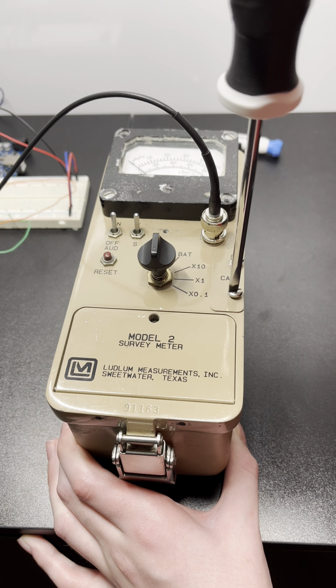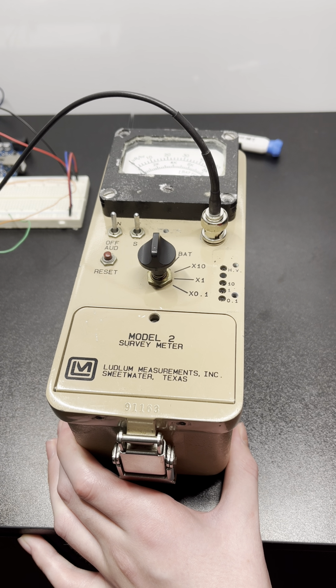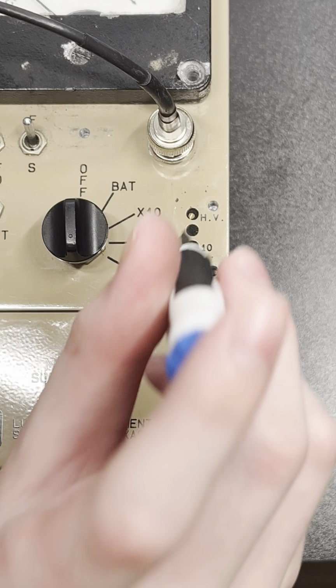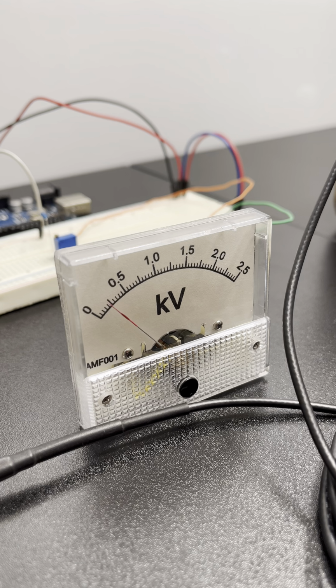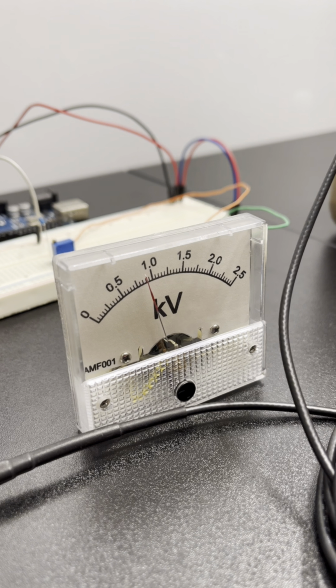I then remove the calibration cover to expose the potentiometer labeled HV. I power up the Model 2 and use a screwdriver to adjust the voltage until the voltmeter reads 900, which is what my chosen probe needs.